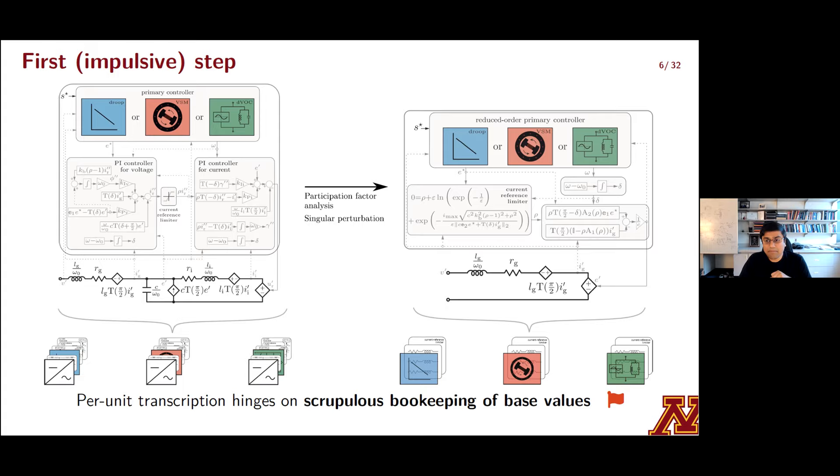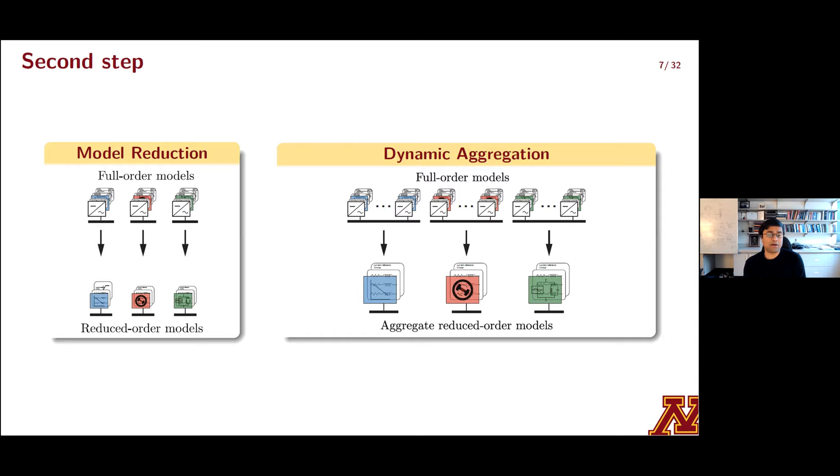So getting back to model reduction, here's another neat result that we stumbled along the way. We know how to get reduced order models for individual grid forming inverters, but what if you had multiple grid forming inverters connected in parallel at a single bus? So it turns out that with appropriate parametrization, you can still get a reduced order, structure preserving dynamic aggregate in such settings under some basic homogeneity assumptions with regard to parameters.